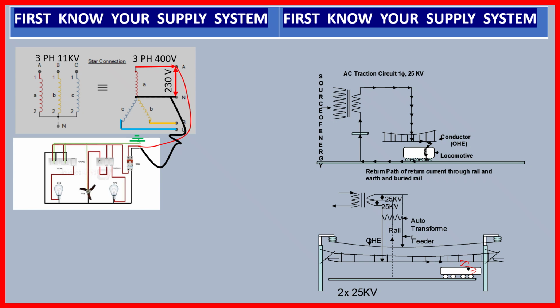We must ensure continuity - it must continue. We are taking alternate connections to protect it so it will not cut. Another system is 2 into 25, with the same principle, just like a mid-tap transformer. The mid portion is connected to the track, one end is connected to the OHE, and another end is connected to the feeder. So OHE to track is 25 kV, feeder to track is 25 kV, but feeder to OHE conductor it is 50 kV.